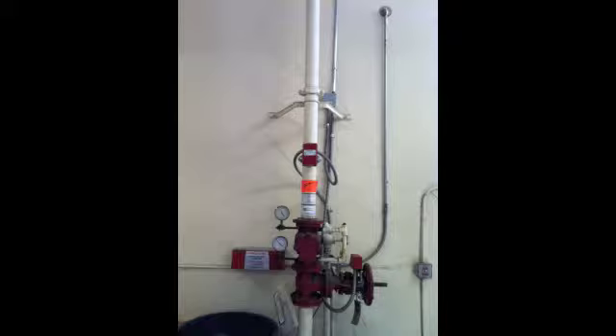If you look to the bottom right of the picture, you'll see the outside screw and yoke valve, also known as the OS and Y valve switch, with the stem sticking out. This is the valve in the full open position. To shut the valve off, you twist that wheel till the stem is fully in. You have to remove the chain and deactivate the tamper switch behind the wheel so the alarm does not sound, alerting that the valve has been messed with.